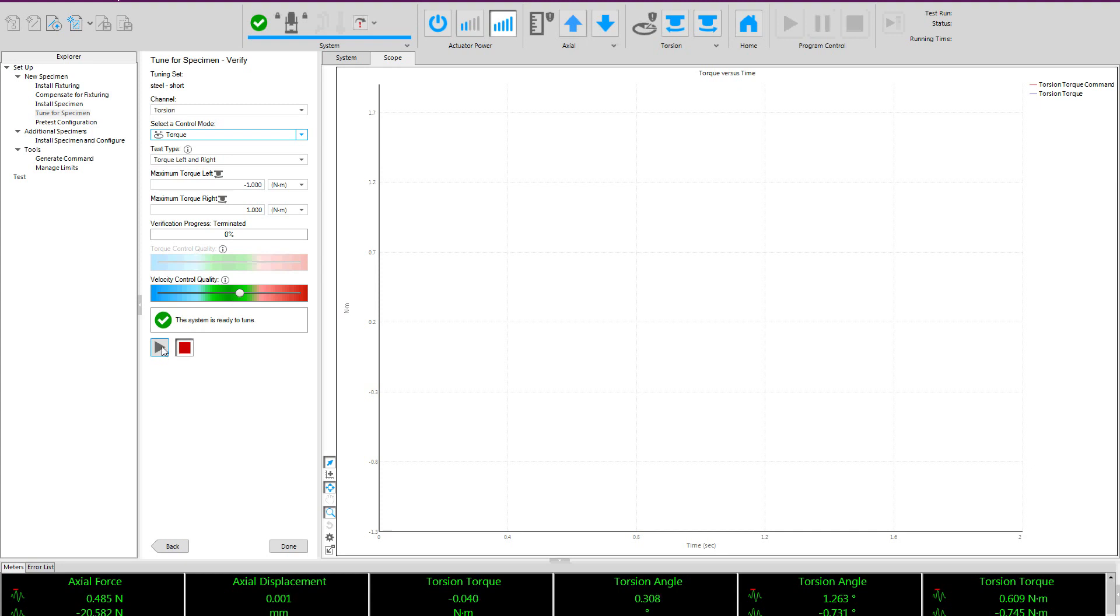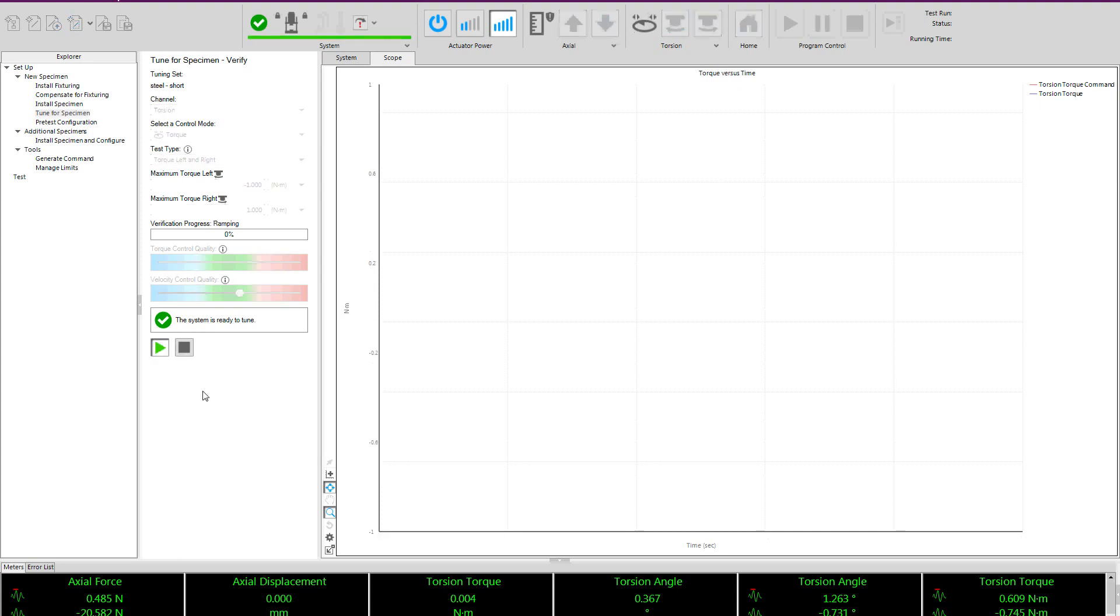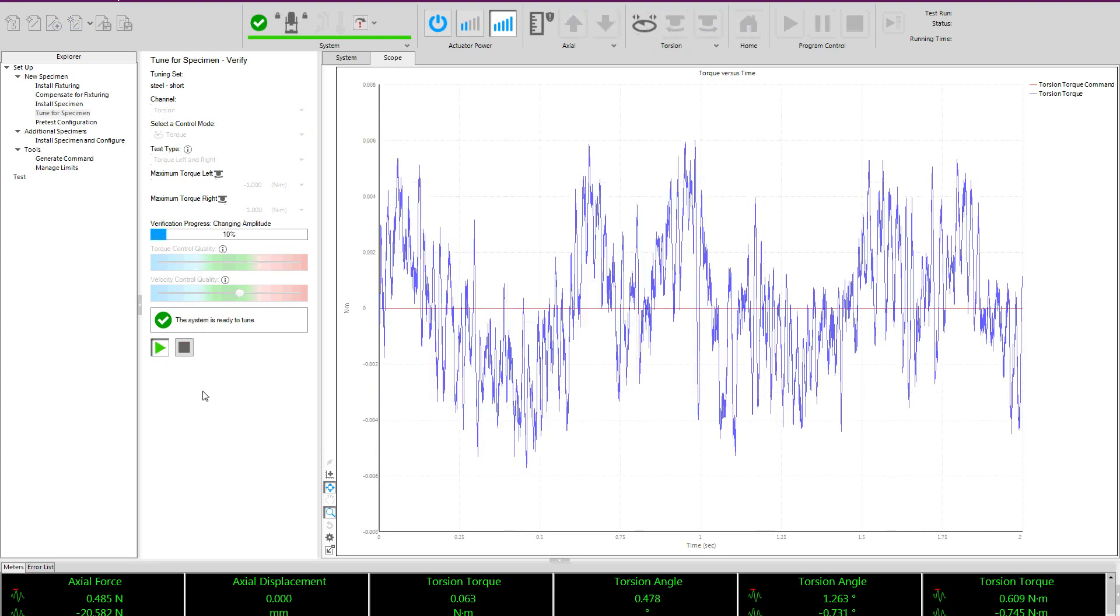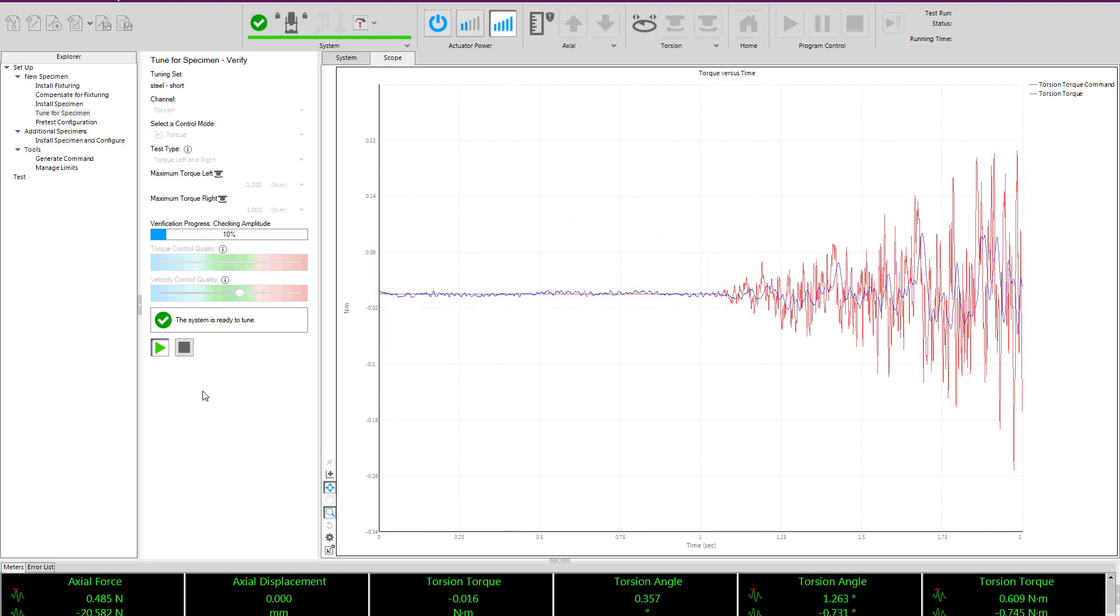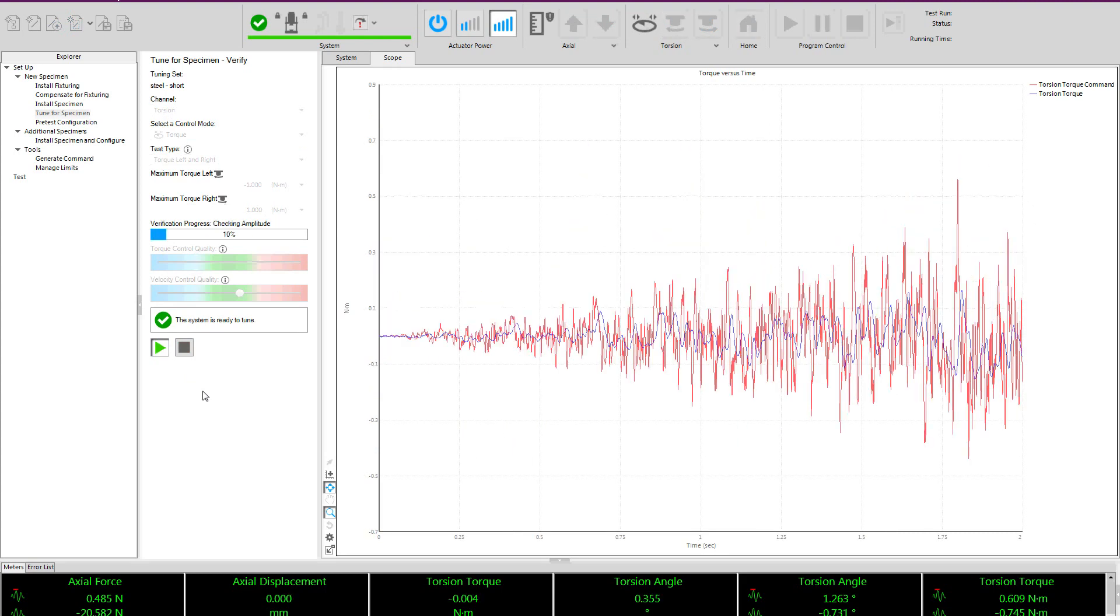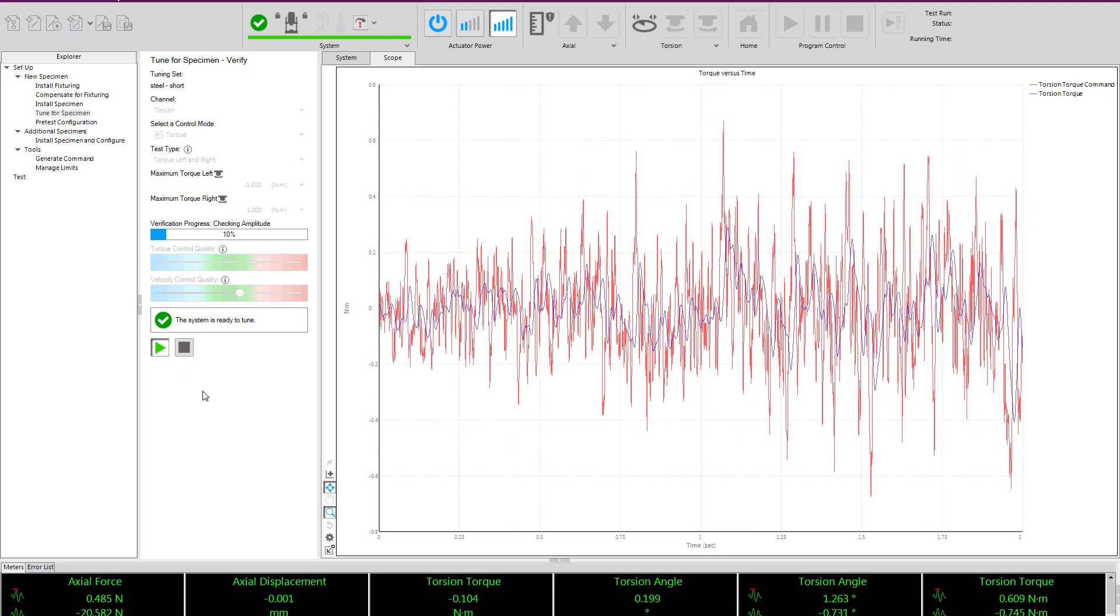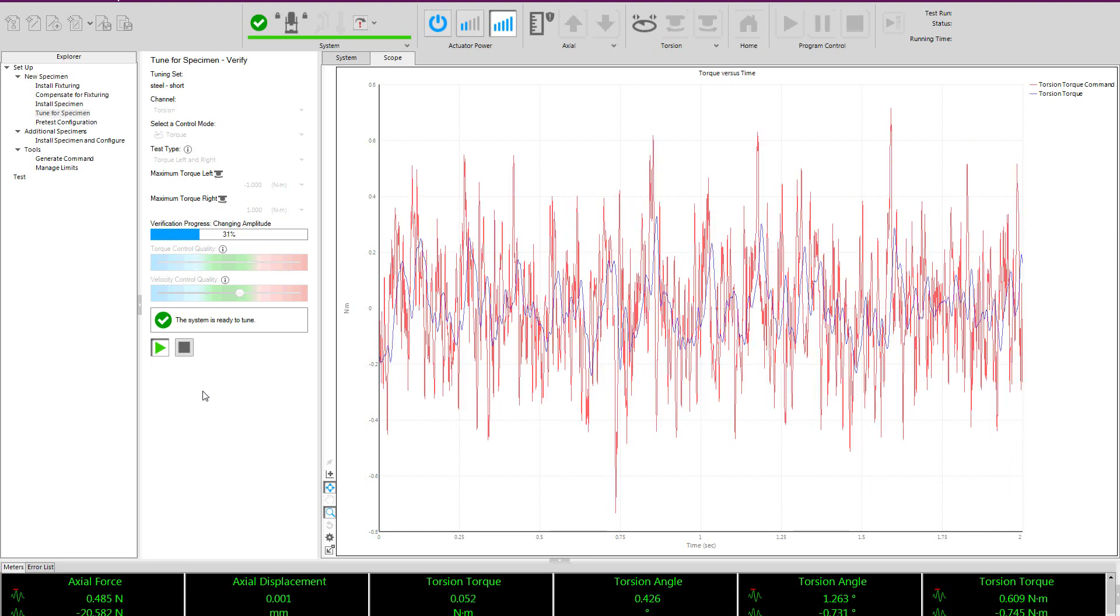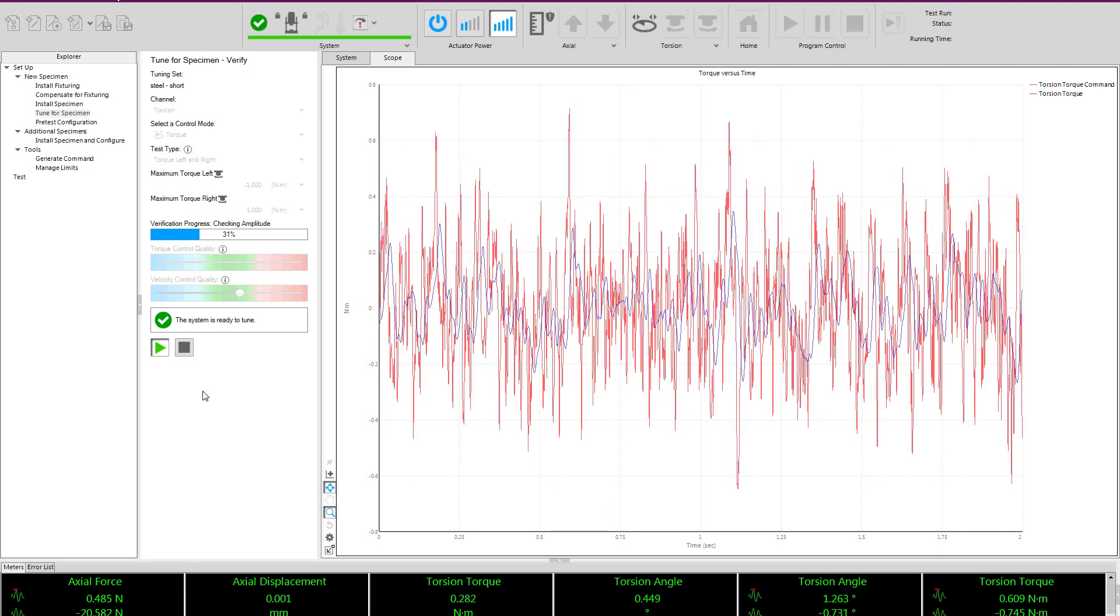So here I will use the same torque values and start the procedure. The procedure looks very similar, but you will note that it is now running in the torque control mode, not the stable angle control mode.